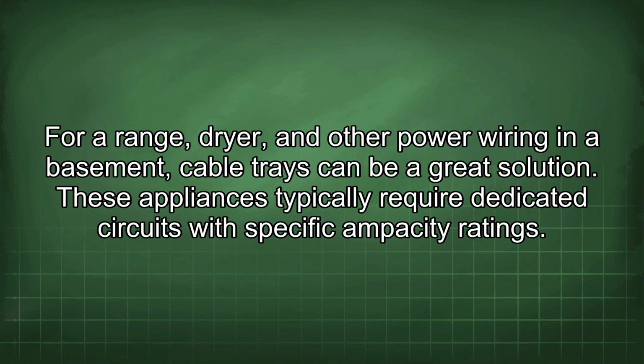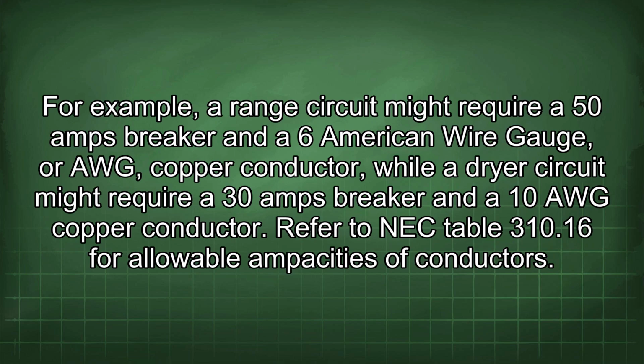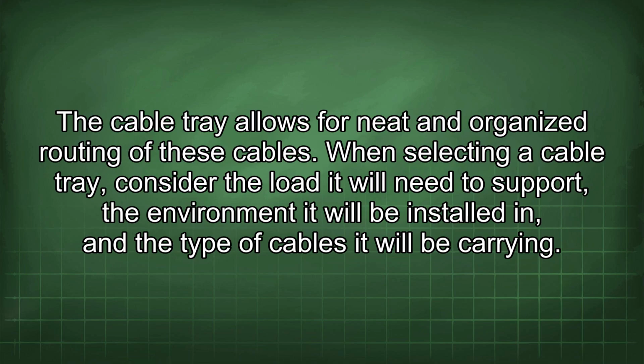For a range, dryer, and other power wiring in a basement, cable trays can be a great solution. These appliances typically require dedicated circuits with specific ampacity ratings. For example, a range circuit might require a 50 amp breaker and a 6 American Wire Gauge, or AWG, copper conductor, while a dryer circuit might require a 30 amp breaker and a 10 AWG copper conductor. Refer to NEC Table 310.16 for allowable ampacities of conductors. The cable tray allows for neat and organized routing of these cables.